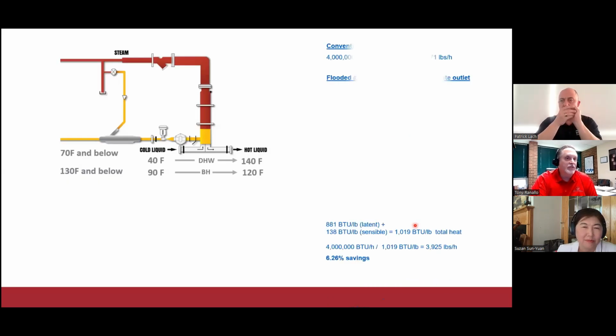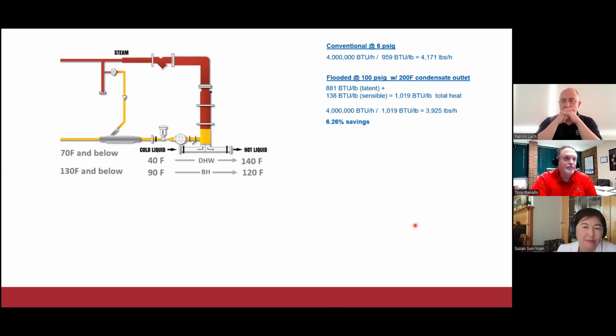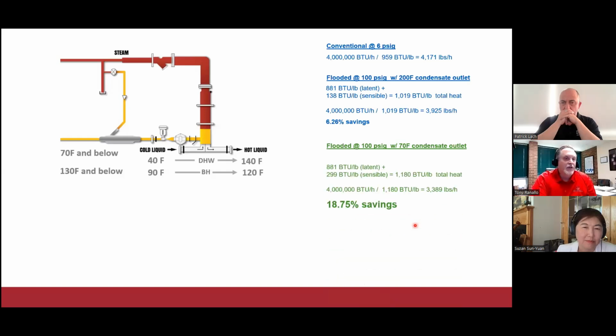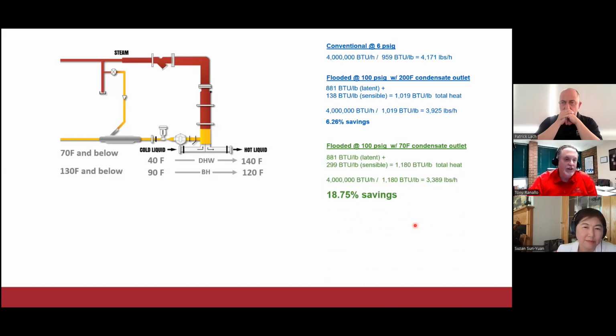Let's look at a couple other scenarios. Again, we looked at the conventional at 6 PSI steam, conventional heat exchanger versus a flooded at 100 PSI at 6.26% savings. If we look at condensate outlet at 70 degrees, let's say that we have a very low temperature, say, oh, maybe we're heating domestic hot water. Well, we can get a very close approach to that, and our condensate temperature can be much cooler. At this point, if you do the math, you'll come up with about an 18.75% savings in steam.